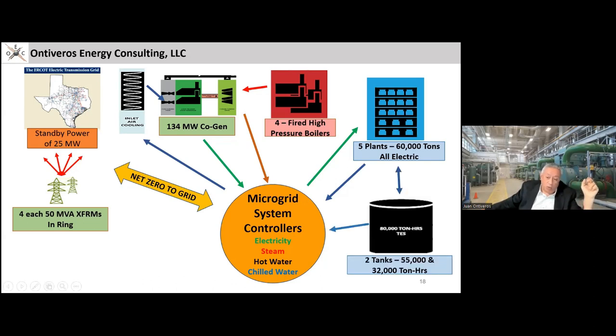And then you have the thermal storage system that allows you to basically reuse energy. Our chiller loads for the campus were actually higher at night than they are during the day because they're producing the chill water for the thermal storage. Well, that sounds like wasteful energy, but not really, because your combustion turbine is most efficient at high load rather than low load. And so the amount of BTUs of fuel to produce that kW is less if it's at a higher load. So that's the objective.